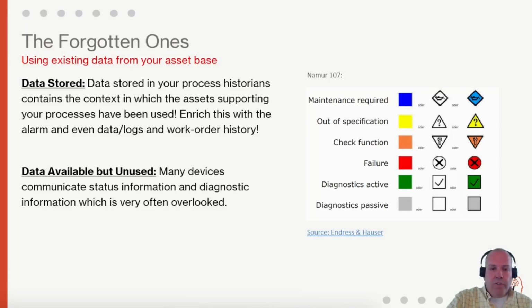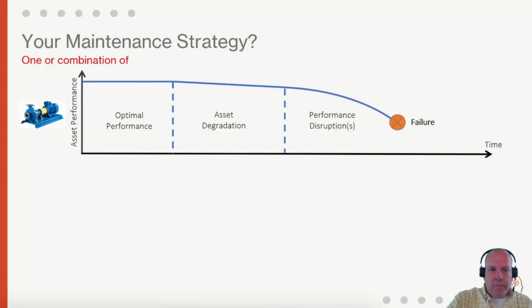Out of specification, the yellow one, is also quite important. It means the device is running outside its permissible range, and as such, it cannot properly support the function it is required to provide anymore. And of course, failure, shown in red, indicates a malfunction of the instrument, sensor, or actuator, which could actually mean you're too late. If you only do inspection rounds, you may lose out on the out of specification, check function, maintenance required signals, etc. You could do things a lot smarter than that.